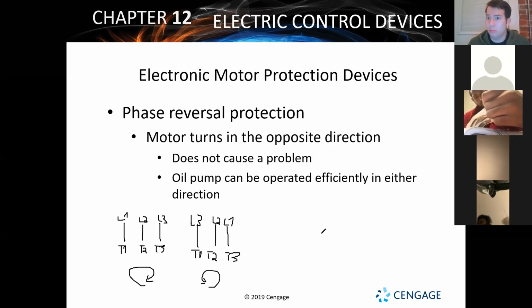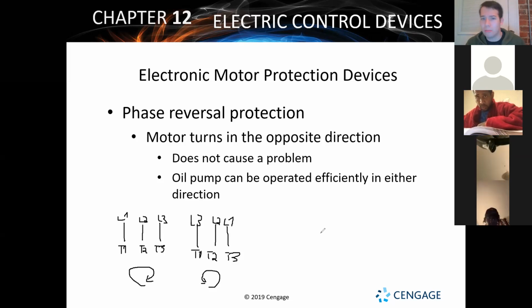Now it says it does not cause a problem. It's true, it doesn't cause a problem. The motor will keep running and the motor will be fine. The problem is you won't get any heating or cooling. Your fan motors are all going to run backwards. So your fan that would normally move air through a building is going to throw air back into a building, basically. That blower motor is going to go the opposite direction. For a compressor, it's going to throw refrigerant in the wrong direction. For an inducer draft motor, it's going to pull the flue gases out in the wrong direction. So that's what will happen.